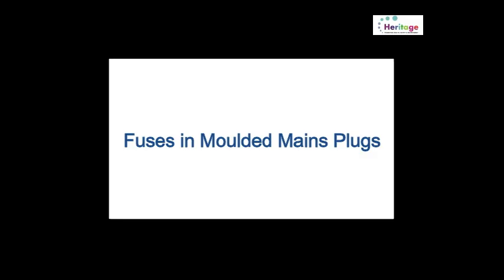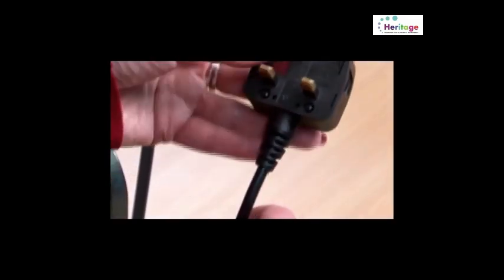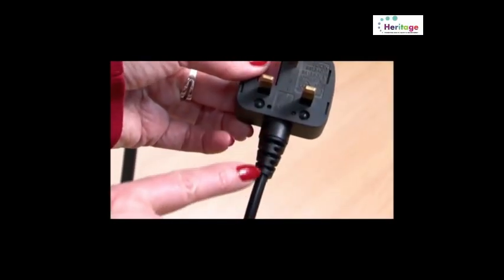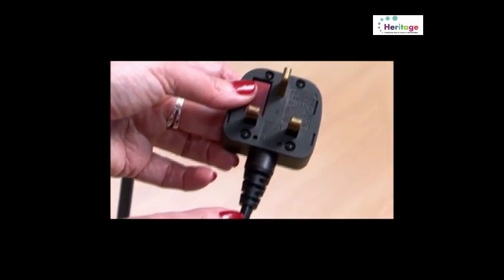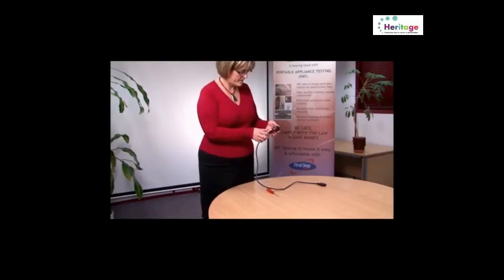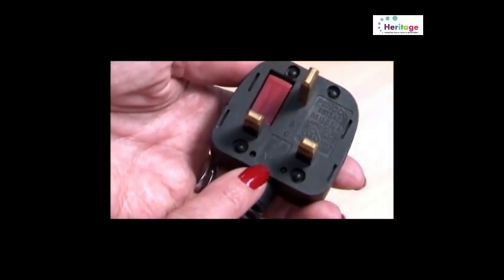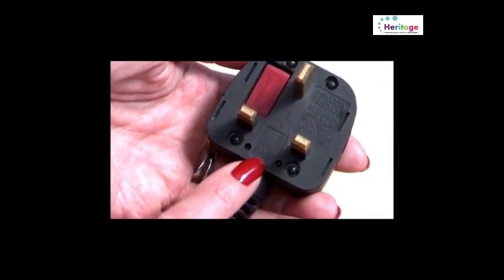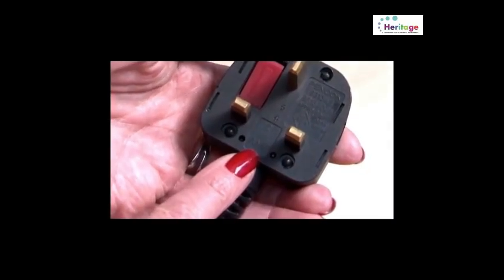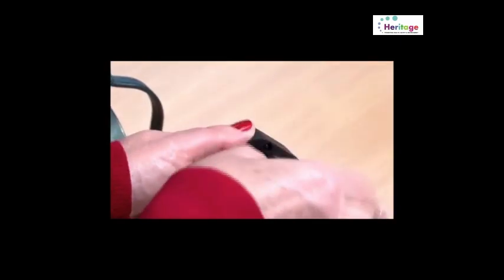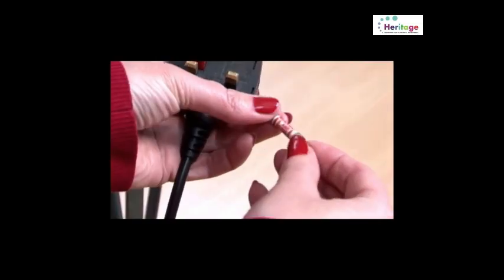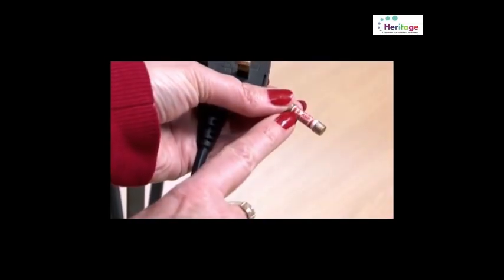Fuses in moulded mains plugs. As these plugs are moulded to the cable, the fuse in these can be fixed by the manufacturer. They know what the maximum current is that the cable can carry, and the fuse is selected to protect the cable and blow if the current exceeds the capacity of the cable. The value of the fuse that is fitted is marked on the outside. All you have to do is to check that the fuse fitted is the same or lower than that marked on the plug. Here the moulded plug has to be fitted with a 3 amp fuse, as this is what is moulded on the plug.